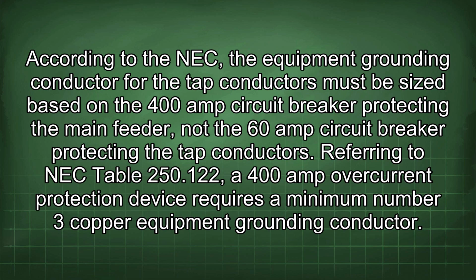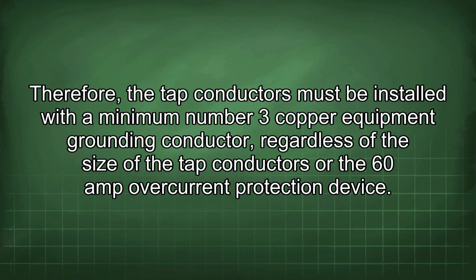Referring to NEC Table 250.122, a 400-amp overcurrent protection device requires a minimum number 3 copper equipment grounding conductor. Therefore, the tap conductors must be installed with a minimum number 3 copper equipment grounding conductor, regardless of the size of the tap conductors or the 60-amp overcurrent protection device.